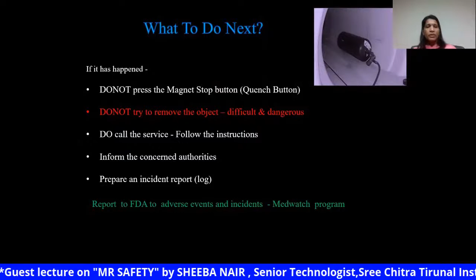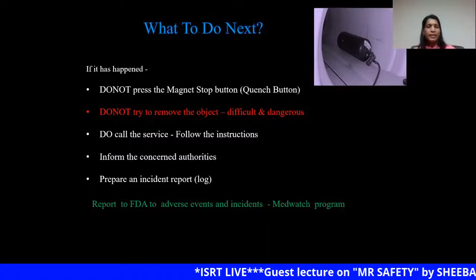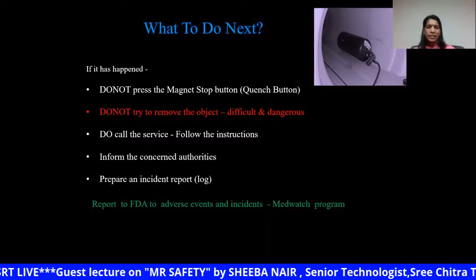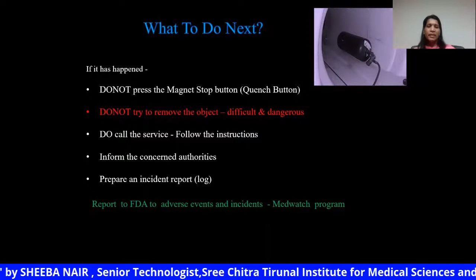So what to do when such an incident occurs? Do not press the quench button immediately. See if anyone is pinned or if there is a safety risk for the individual. Do not press the quench button. Do not try to remove the object, as this can produce additional hazards. What you have to do is inform the MR safety officer first. Then, second, call the MR engineer, and they will give you instructions, and you have to follow them. The FDA demands that any such adverse event should be reported to the FDA so that it can put out guidelines and we can prevent such incidents from occurring in other institutions in future.